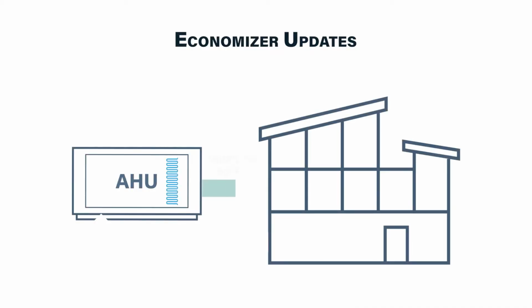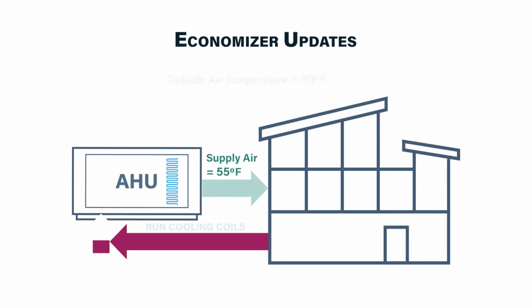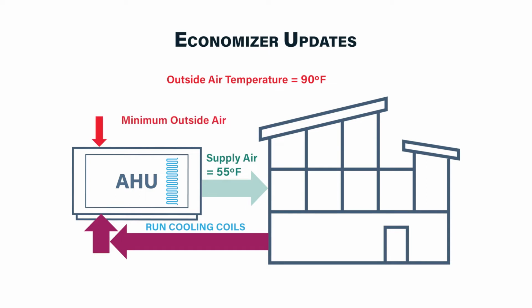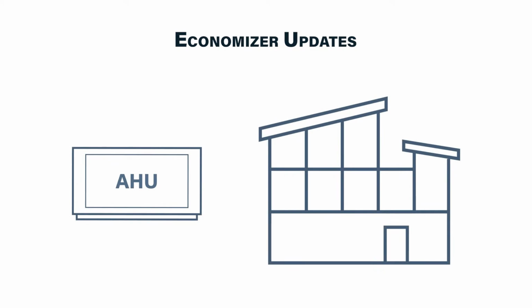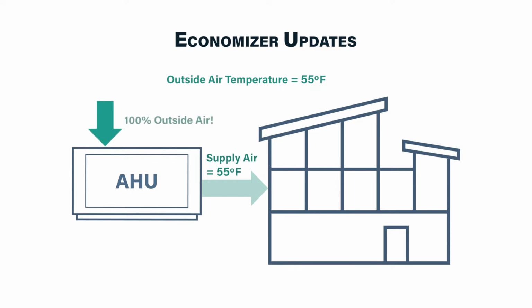Here's a quick example of an air side economizer. On really hot days or really cold days, we typically only want to bring in the minimum outside air we need to, just to provide ventilation for the building. This is because cooling that air in the summer or heating it in the winter would use a lot of energy. However, since we typically supply air to the building at 55 or 60 degrees, then if it's 55 or 60 degrees outside, it's more economical to bring in that cool outside air to cool the building, instead of reconditioning the warmer room air.